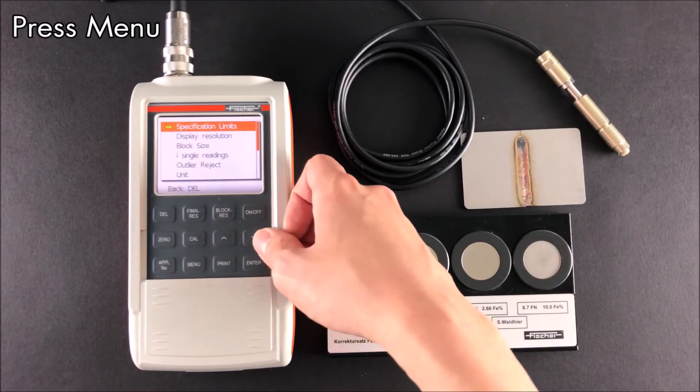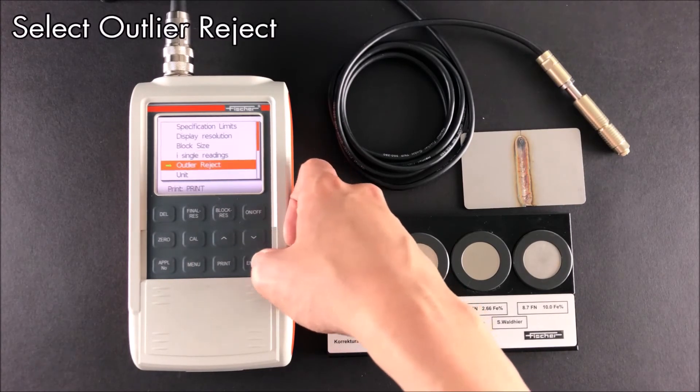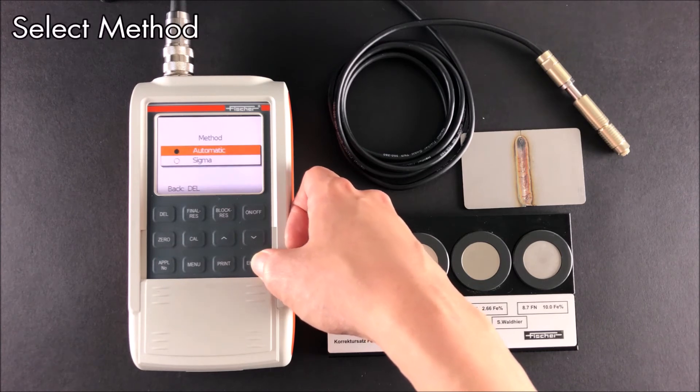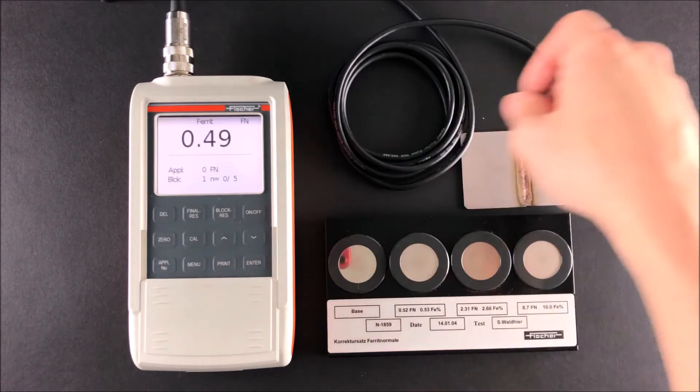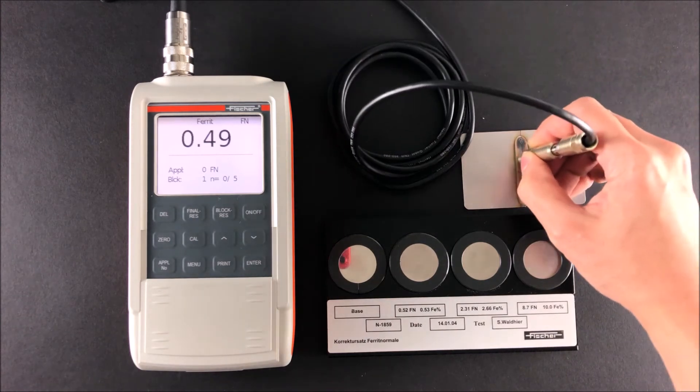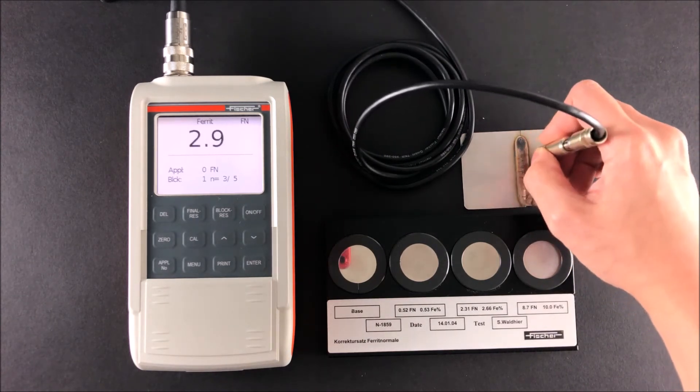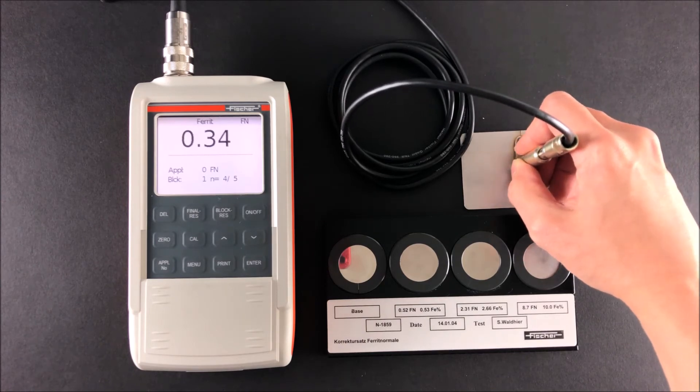Outlier reject can be used to reject readings that are distant from other readings. Automatic rejects readings based on limits set, while sigma rejects readings based on sigma limits. Measurements that are recognized as outliers during outlier rejection are not included in the statistical evaluation.